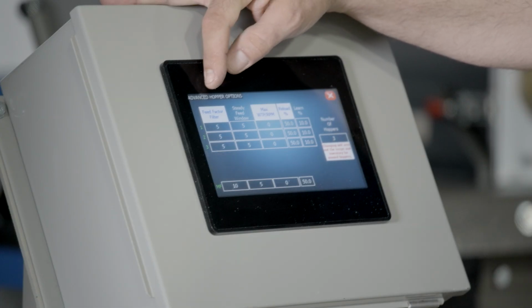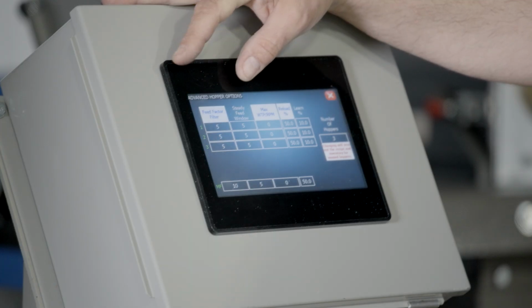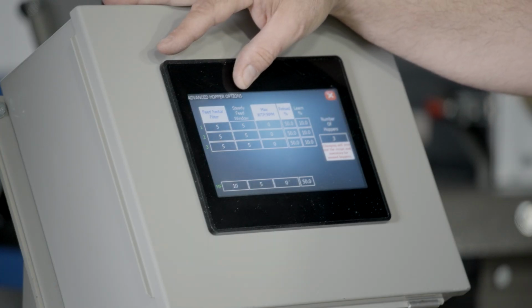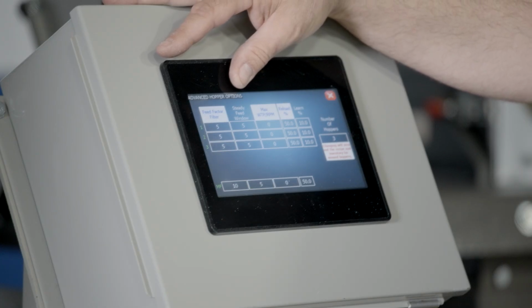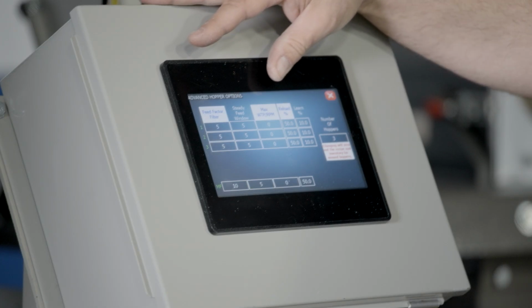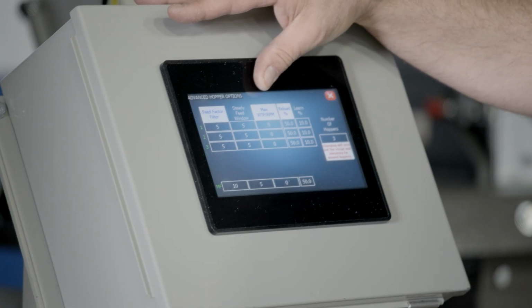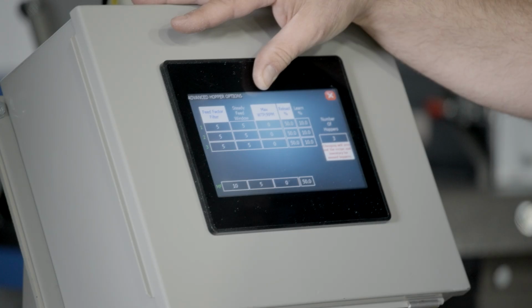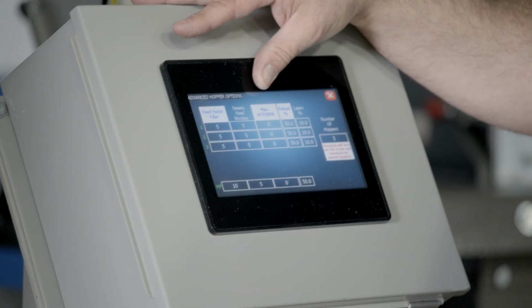So we have a feed factor filter. That's the number of samples we take to put into the first in, first out table. We have a steady feed window. That's the variation around the median that the samples can be and still be acceptable. Max weight throughput per RPM. So you can set a value in there to limit the weight throughput per RPM value.